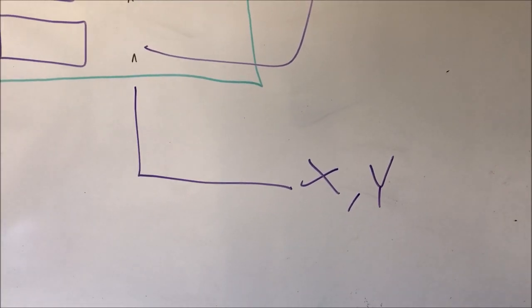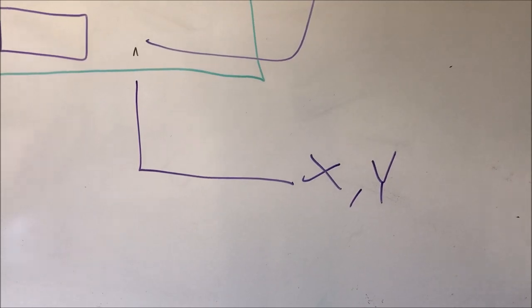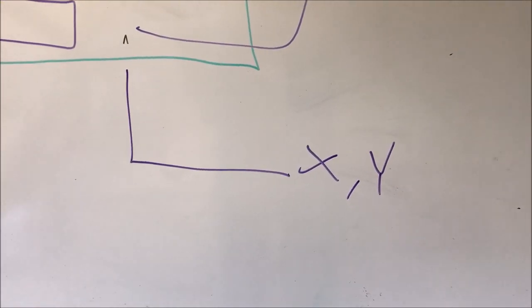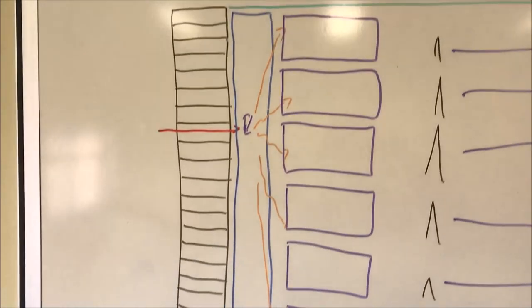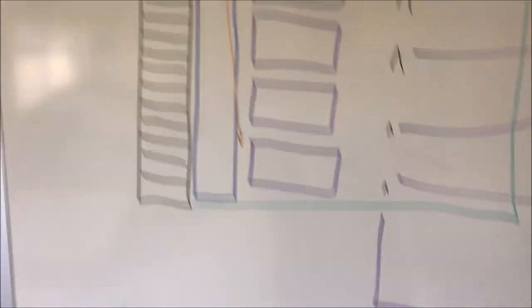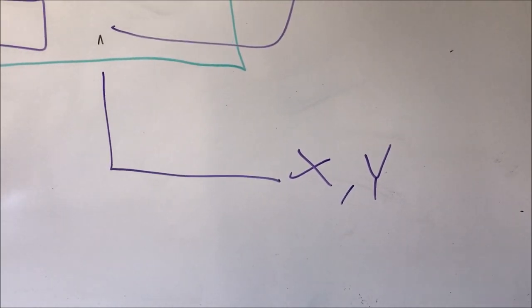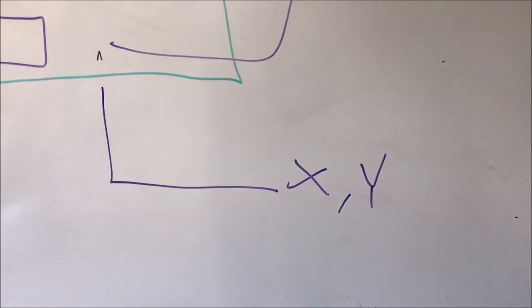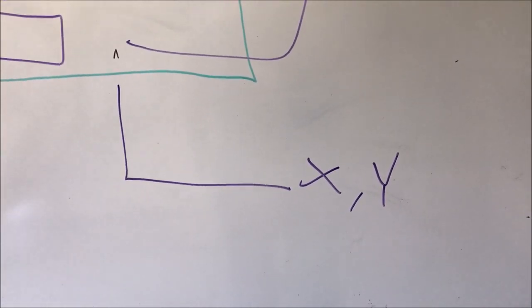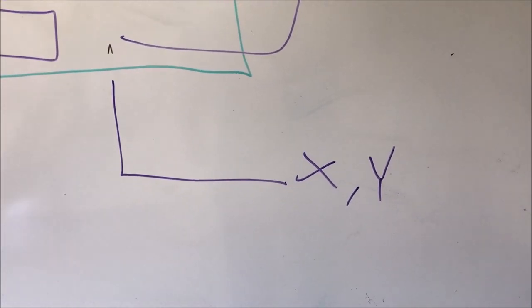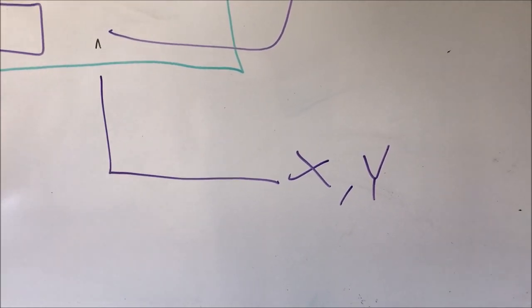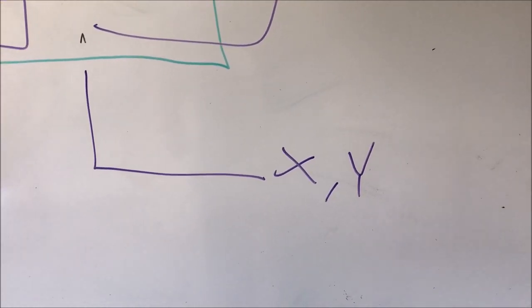So the position circuitry gives us an X and a Y coordinate. When you look at the position circuitry on both the X and Y plane based on those amplitudes, you end up with an X and Y coordinate of where an individual event occurred — essentially a dot on the screen — but it still has to go through the pulse height analyzer next.